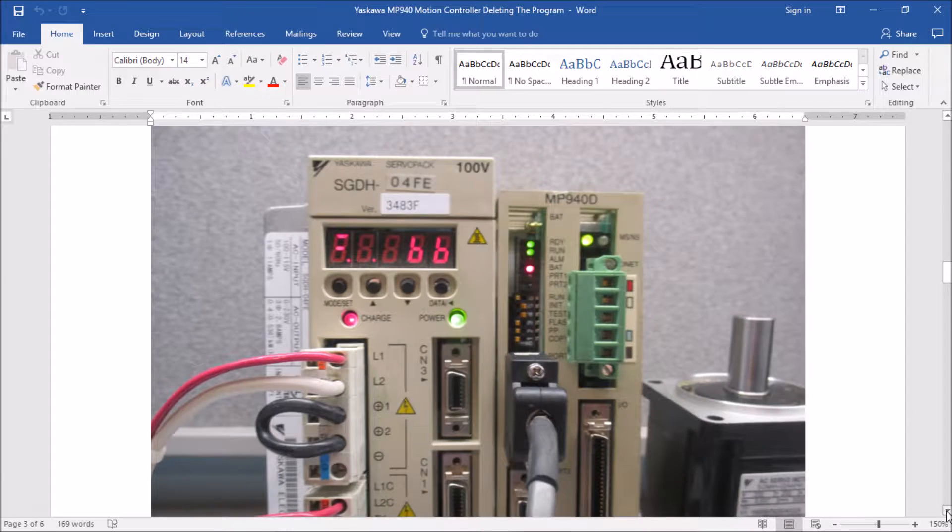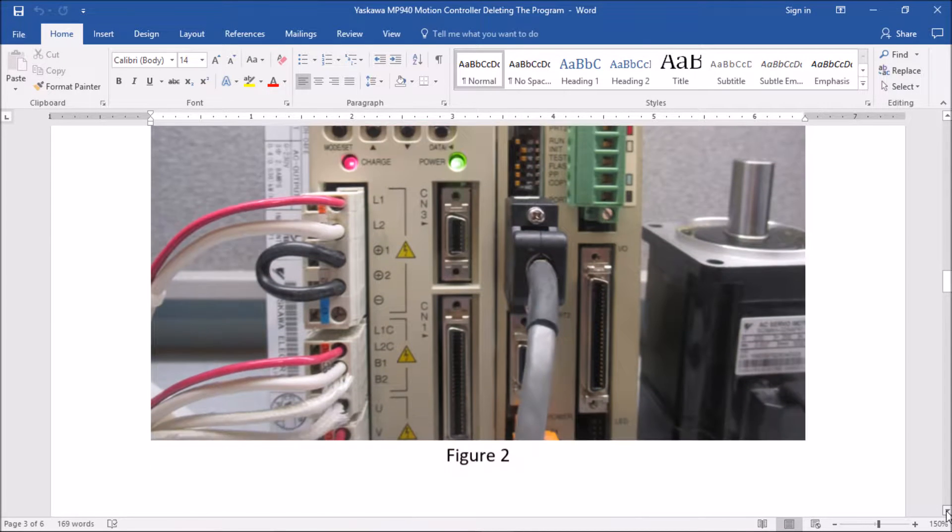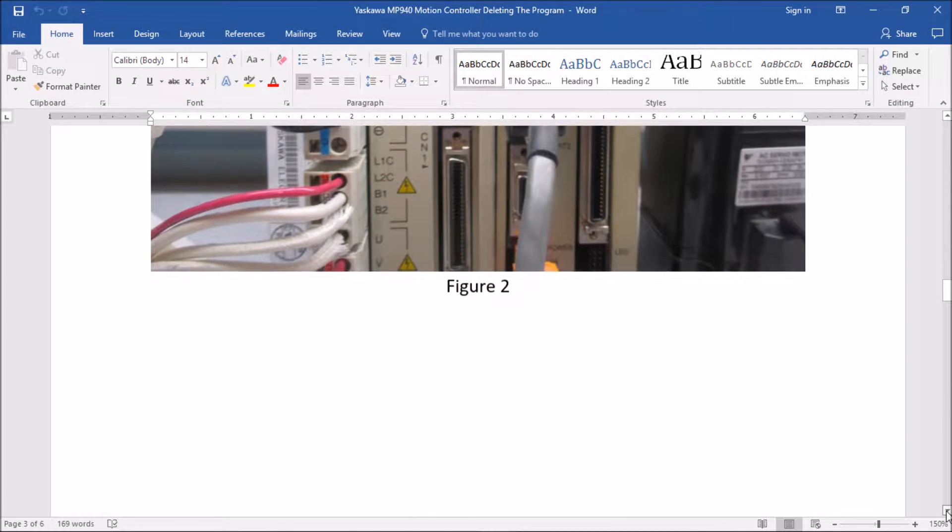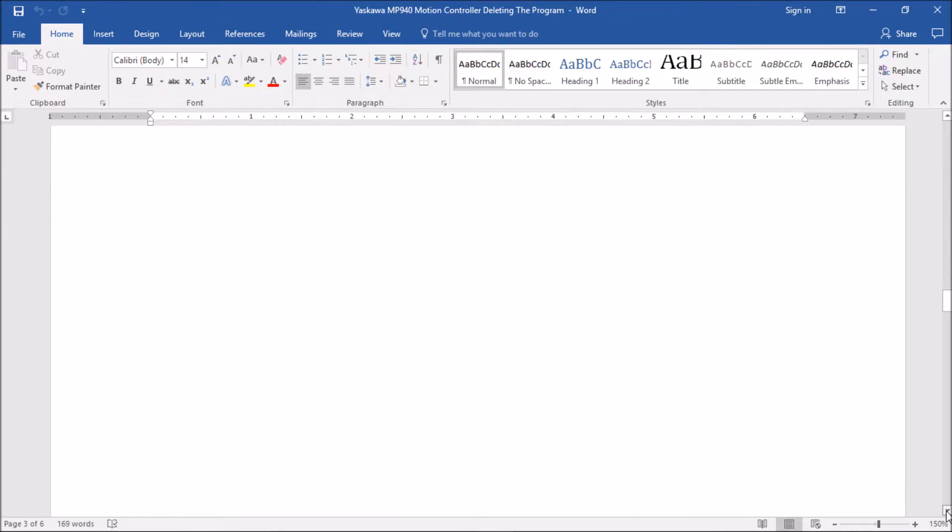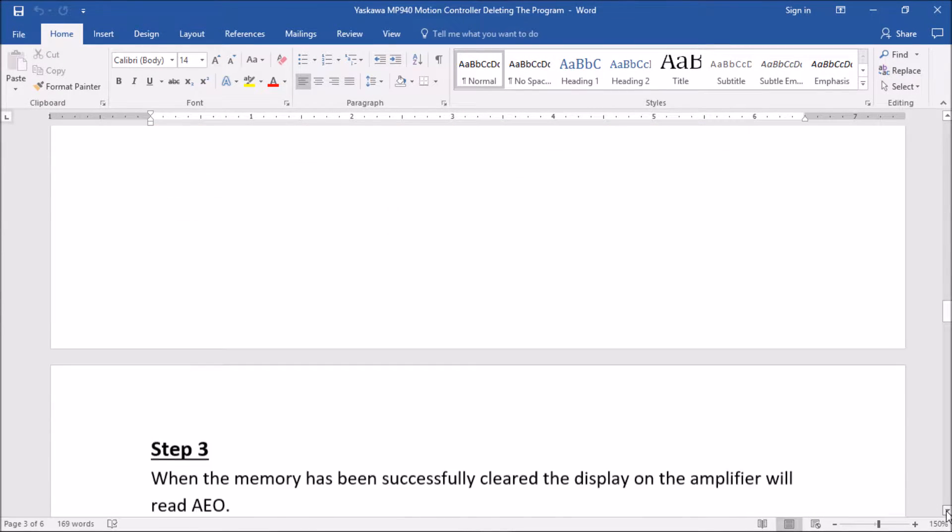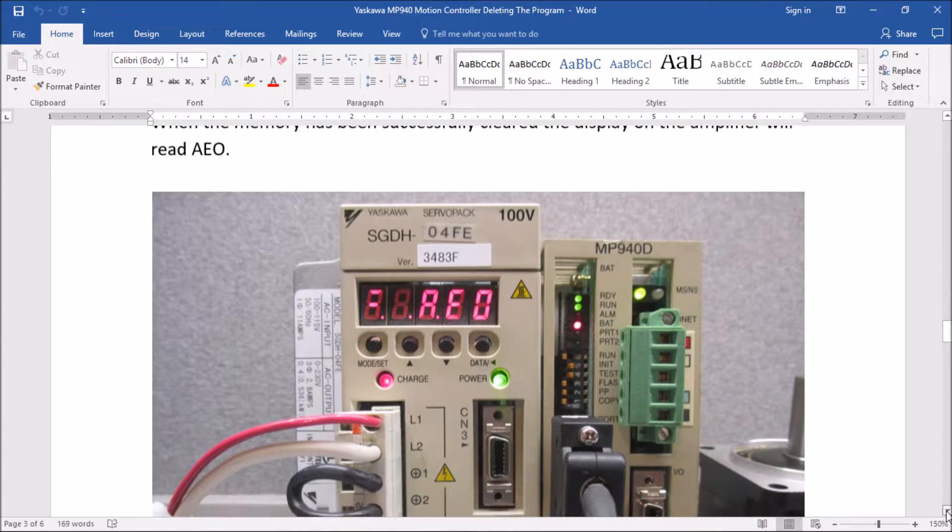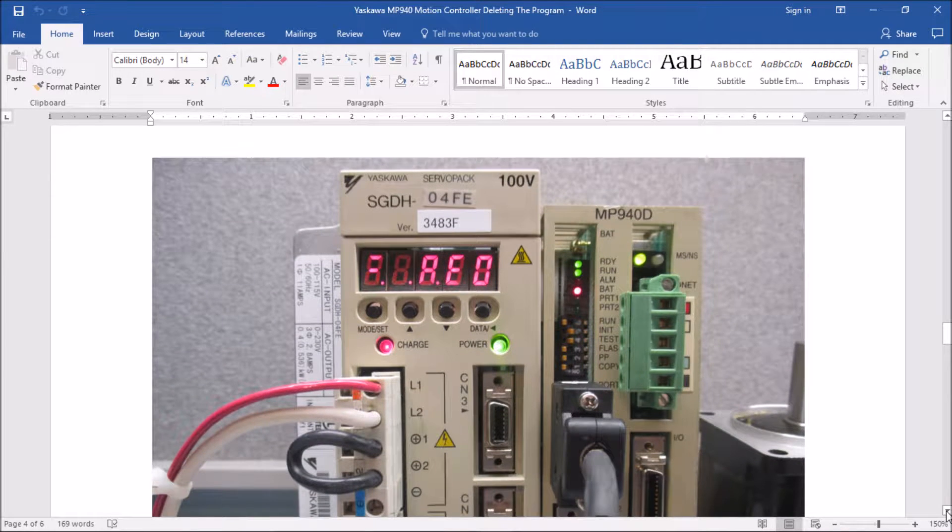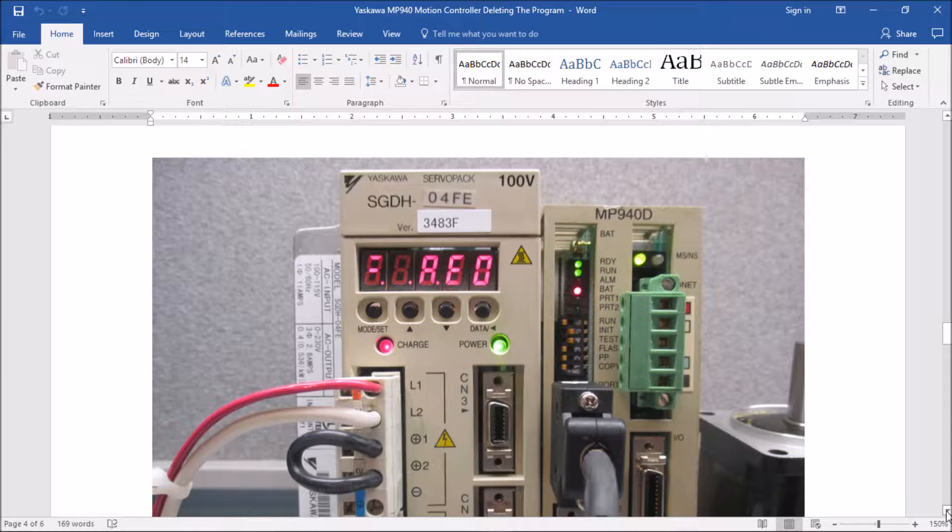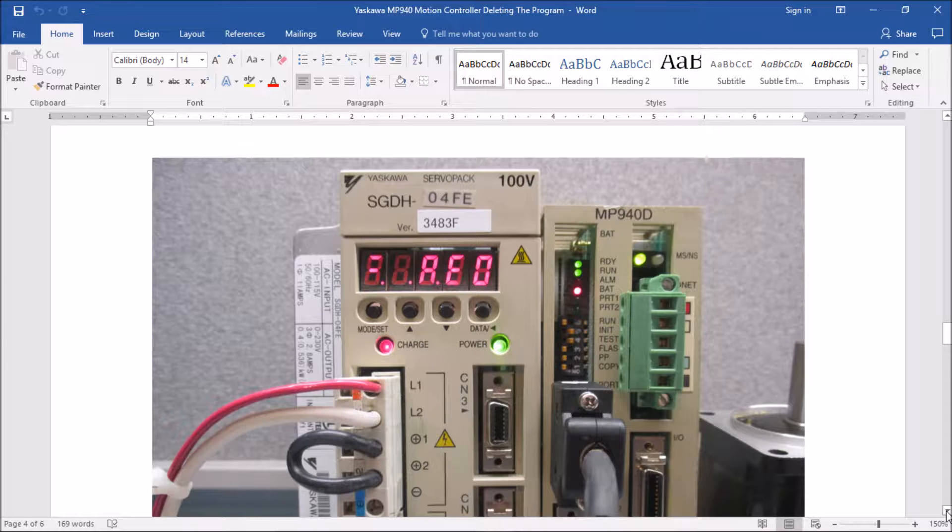Now on to step three. Once the program has been erased from the memory, you should have an AEO displayed on the amplifier. Now this is just an option board alarm that it's not seeing the option board most likely. But the ready and the run LEDs will continue to flash on the MP940.